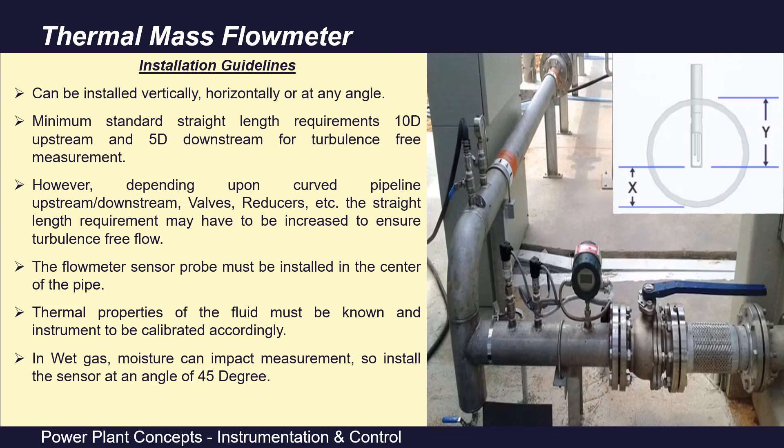Next is, as I already mentioned, this is insertion type. So this sensor, which has basically two sensors, one is reference and second is heated. So these sensors must be at the center of the pipe diameter. The flow sensor probe must be installed in the center of the pipe.